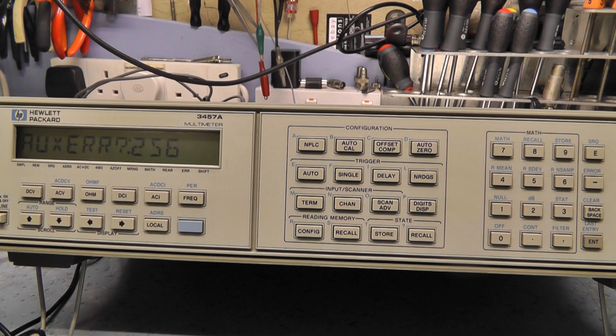According to this, auxiliary error 256 is AC attenuator frequency compensation beyond tolerance. Press AC, perform an AC converter frequency response adjustment, paragraph 5-7 in the manual, and repeat steps D through H of this process. So the manuals, as always with Hewlett-Packard stuff, are very clear.